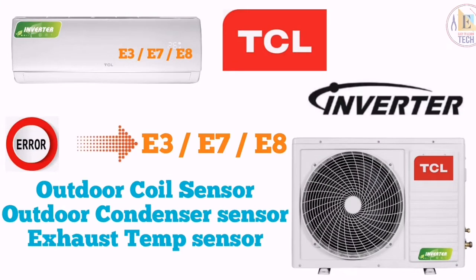When we see error E3, E7 and E8, it means outdoor sensor faulty. In the outdoor we have 3 sensors: the outdoor coil sensor, the outdoor condenser sensor and the exhaust temperature sensor. These all 3 sensors are connected to a single plug. First of all, you have to check that the temperature sensor of the outdoor power source board is in good contact with the slots CN1 and CN2, and if it is not connected properly, insert it again and try to turn the unit on and see if the error comes again or not.